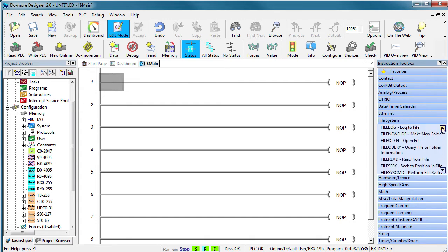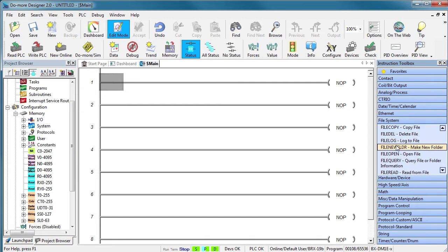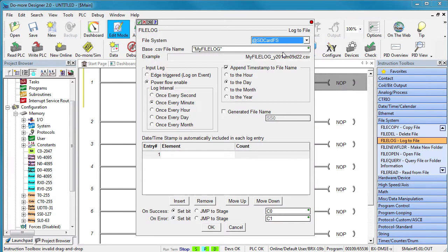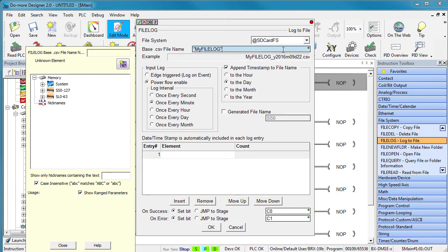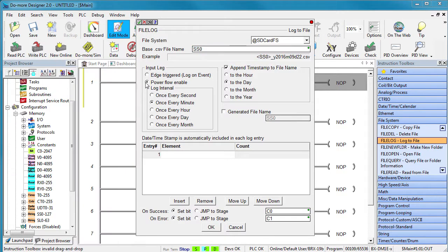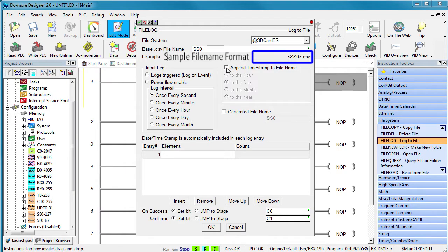You can skip all this stuff and just grab this one instruction – File Log. Let's send the log to the SD card. We'll use short string 0 for the file name. Let's add a log entry once a second and let's append a time stamp to the file name.